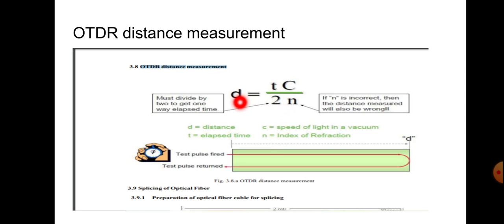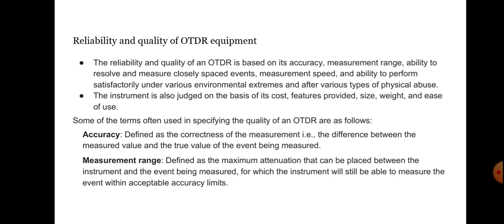OTDR is characterized by its performance parameters, starting with dynamic range. The dynamic range decides the maximum length of fiber over which various measurements can be taken, and it is decided by the total pulse power and the sensitivity of the photodetector. The reliability and quality of the OTDR is based on its accuracy, measurement range, ability to resolve and measure closely spaced events, measurement speed, and ability to perform satisfactorily under various environmental extremes.